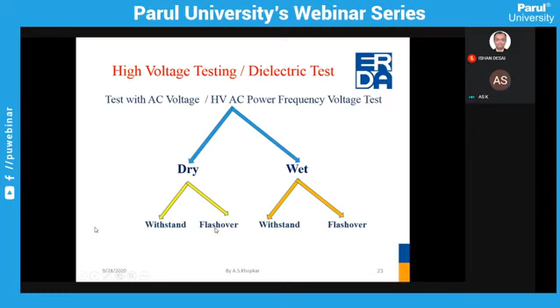To check that, basically all the outdoor equipment like current transformers, potential transformers, insulators, and bushings are tested. Only the transformer is not, because it is hermetically sealed. But in the case of bushings, this wet test is also applicable. The wet test means under artificial rainfall condition, we apply the high voltage. That is the difference between dry and wet. Again, these dry and wet tests are conducted in two ways: one is the withstand voltage and second is the flashover. We'll see how both of these are conducted.